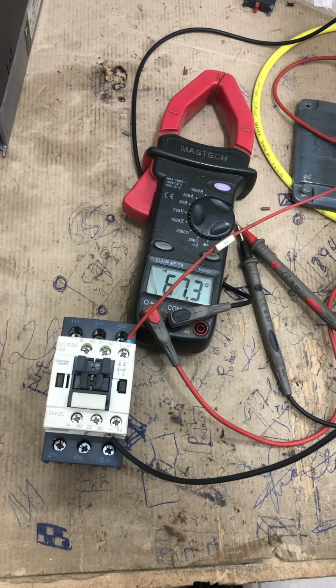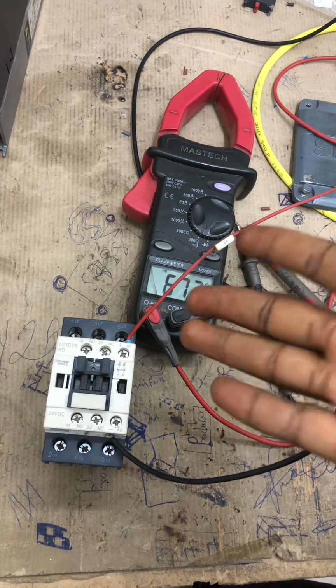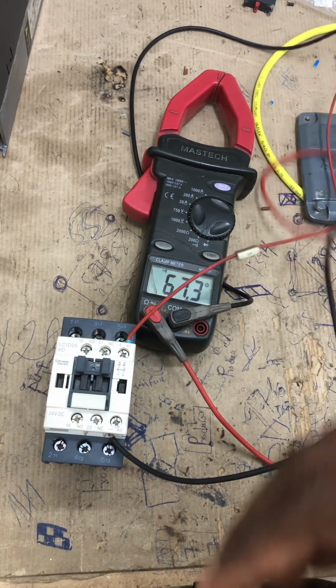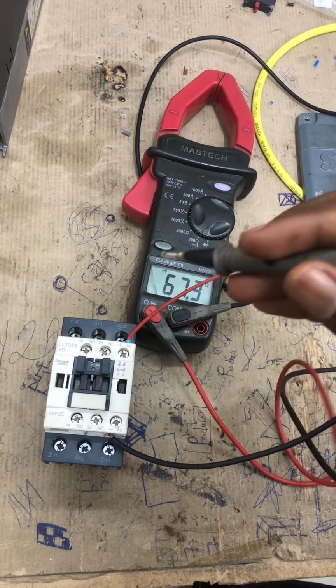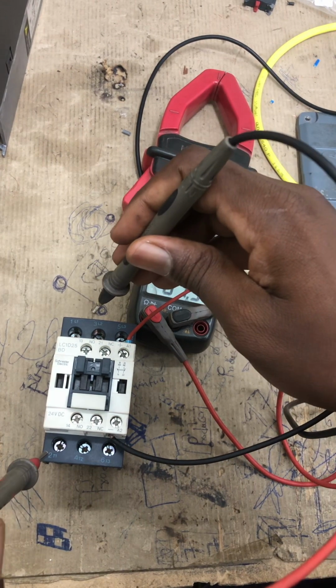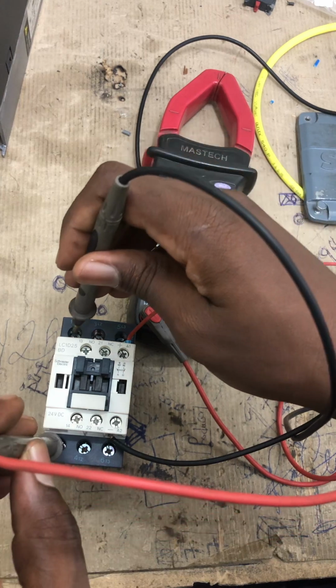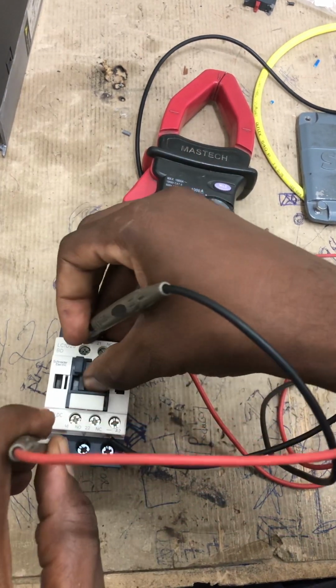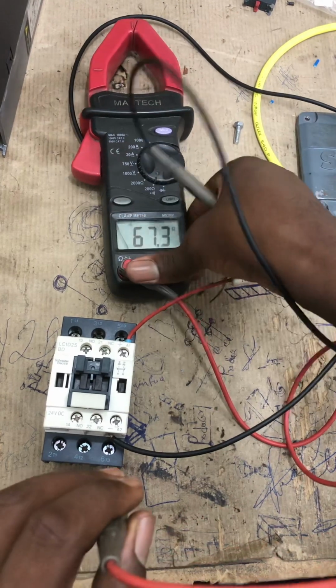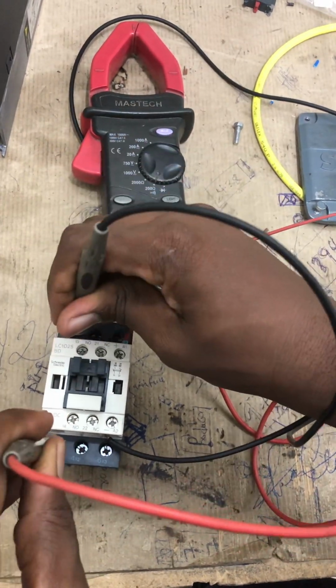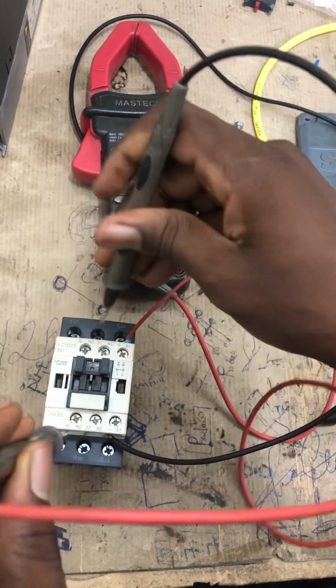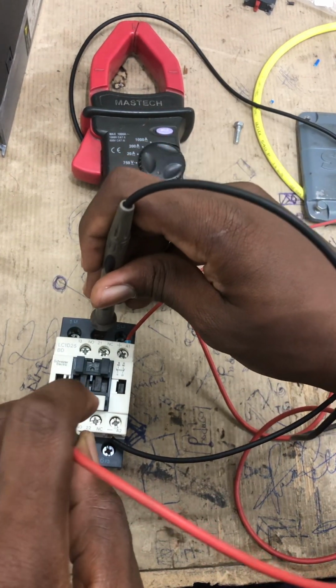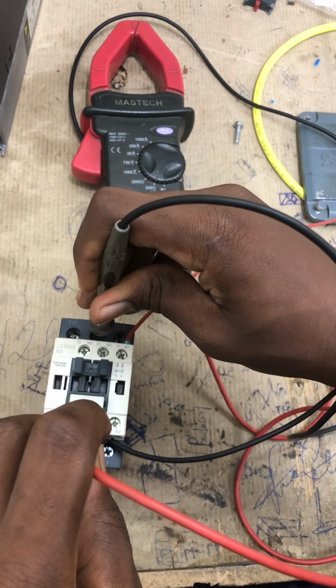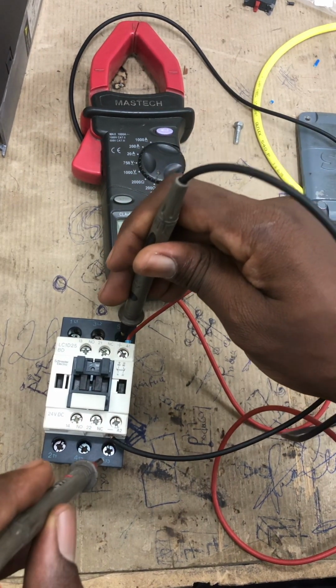So I'll put the 24 volts back in so that we'll run the test on the contactor. So the state has changed. And then, like I said, when the coil gets energized, lines 1 and 2 are supposed to give you a perfect continuity, lines 3 and 4 are supposed to give you continuity, and then lines 5 and 6 are supposed to give you continuity.